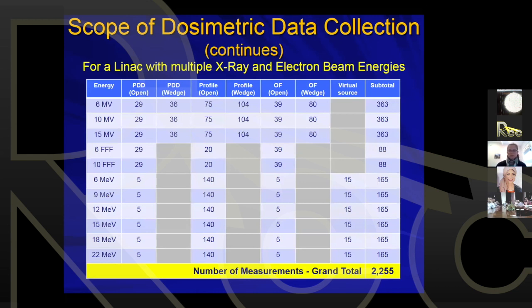Okay. Why is there a difference in duration of commissioning between Varian and others? I think that commissioning duration is dependent upon the number of beams that your machine is producing. Here in our clinic, we have a TrueBeam STX that has 6x with flattening filter, a 10x with flattening filter, a 15x with flattening filter, and then we have a 6 FFF and a 10 FFF. So we have a total of 5 different X-ray beams plus 8 or 9 electron beams. To commission all of them actually determines the amount of time that it takes.